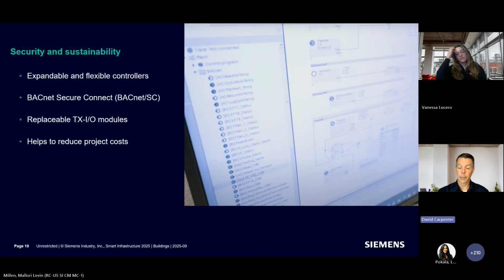For security and expandability, we've seen some pictures of a couple of panels during the presentation. All of the I/O modules are replaceable and able to be added to. That's important because no site is static. They're always growing and changing, equipment is being moved in, and new cooling equipment and new things to be monitored are being added. Instead of replacing an entire controller, an additional I/O module can be added. We're not changing any of the programming on the site, we're just adding a few points, which means peace of mind for the customer because nothing changed from what was already working.